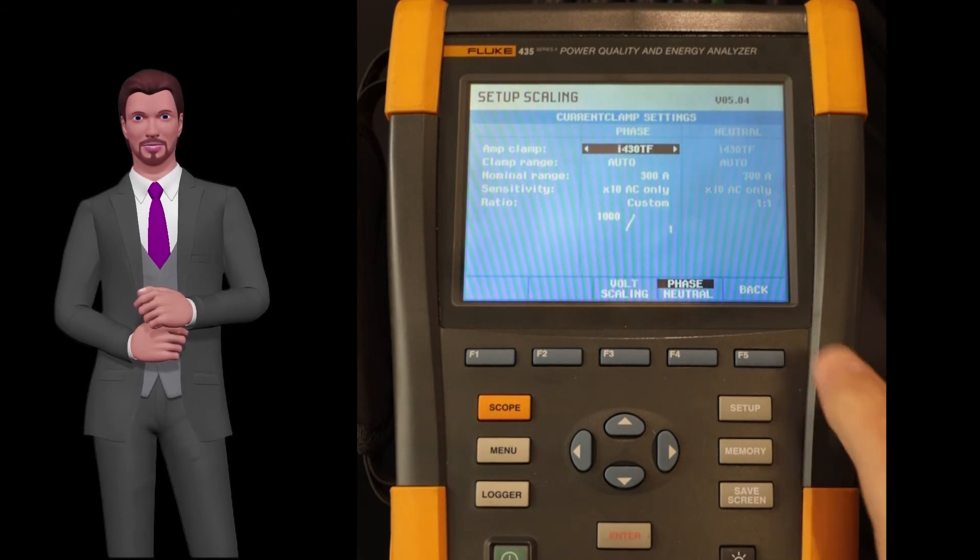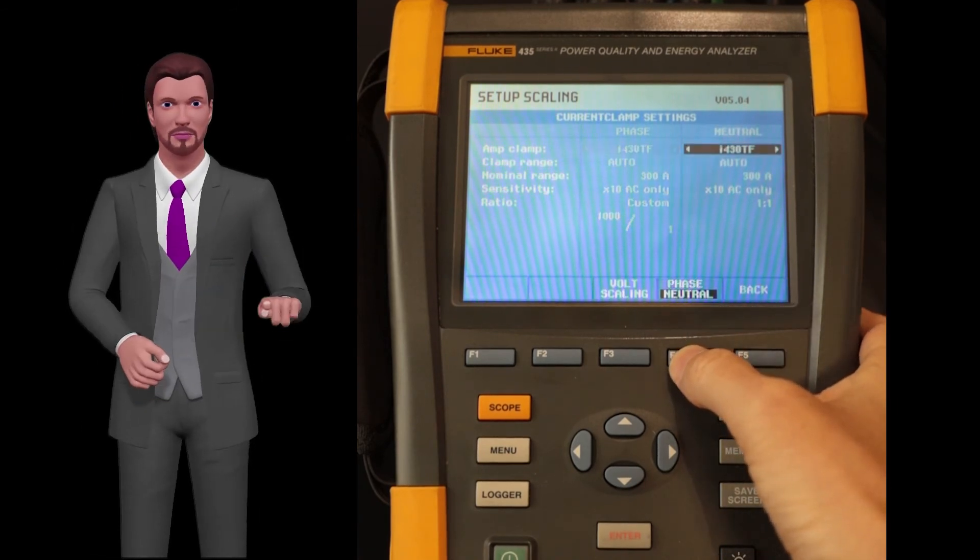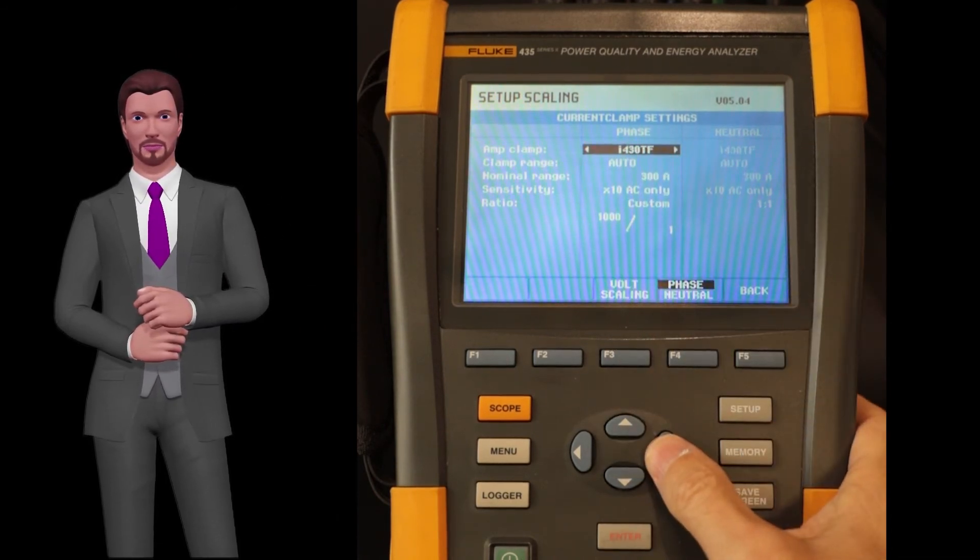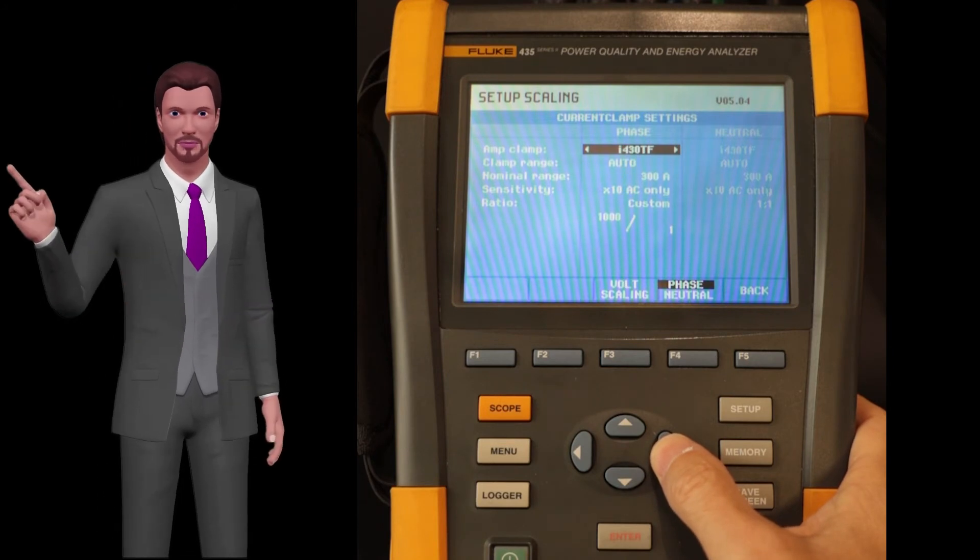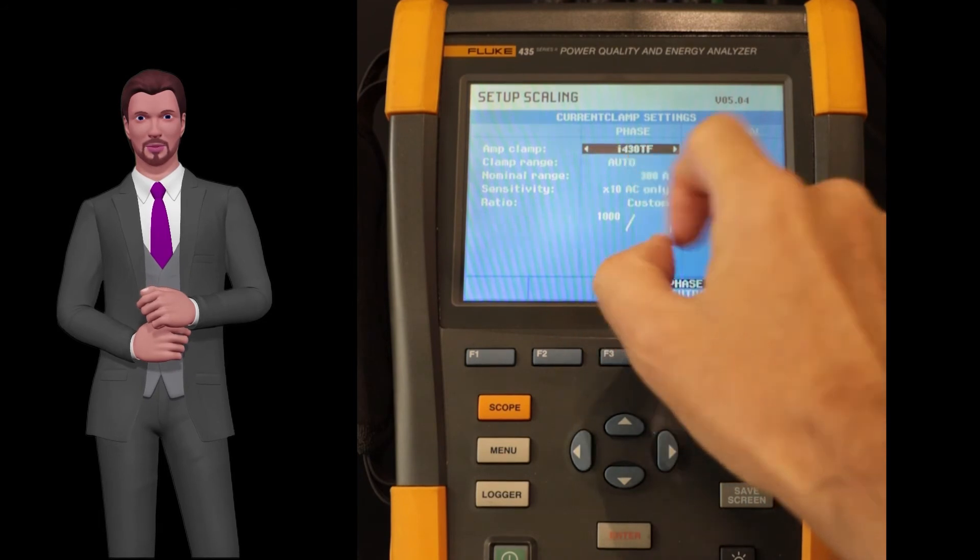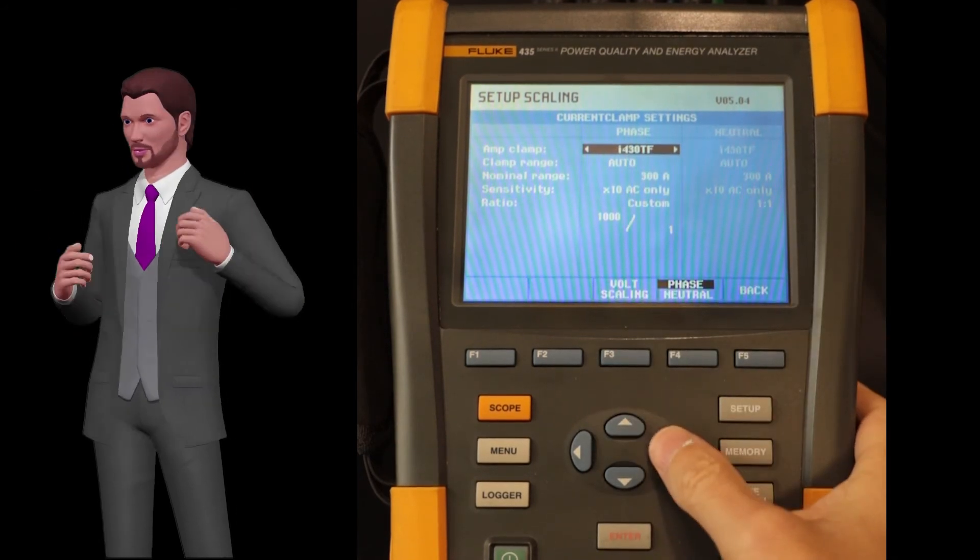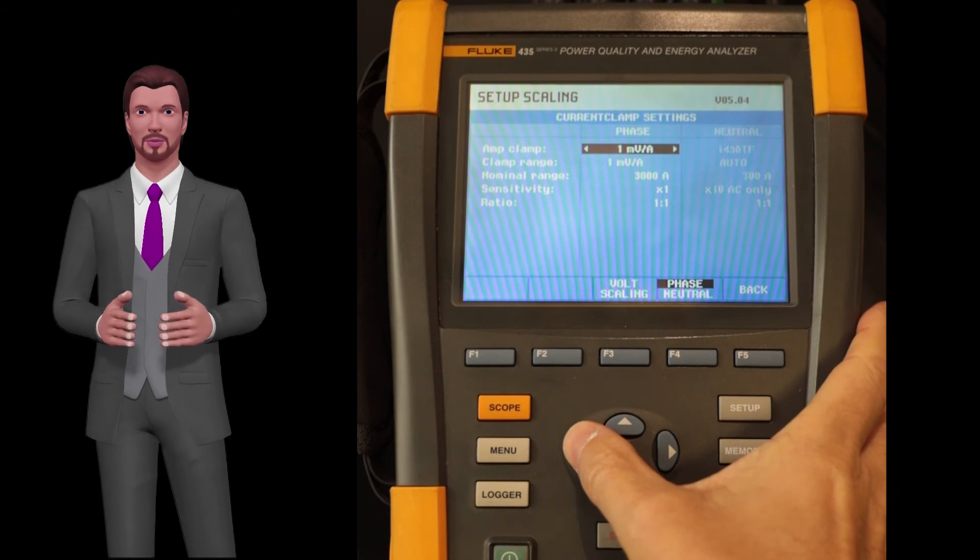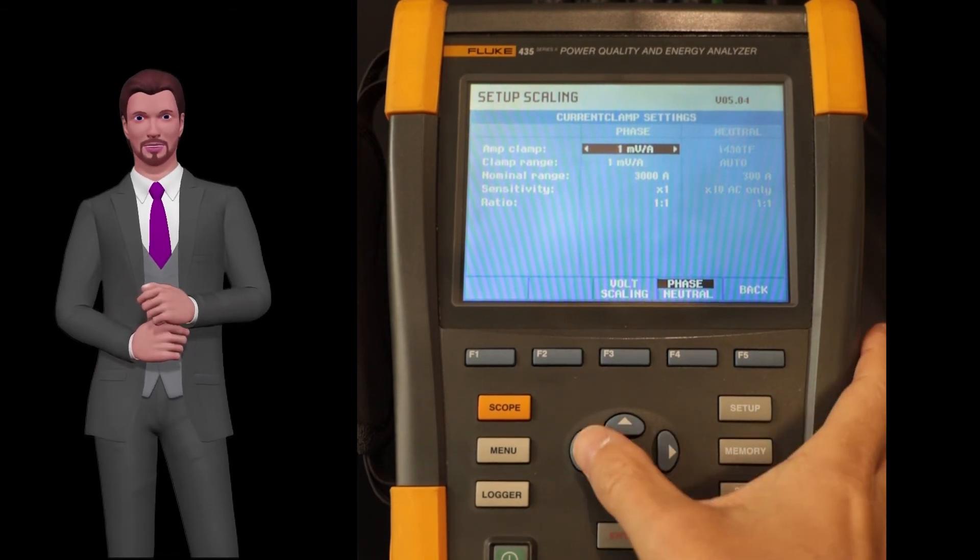We can switch between phases and neutral with the F4 key. The first parameter that appears is the probe model that we are going to use. If the standard flexible probes supplied with the unit are used, this model is indicated as I-430 TF. But if another probe is used, we can change this parameter with the left and right arrows. You can, for example, choose a probe with a given millivolt per ampere output, for example 10 millivolts per ampere.